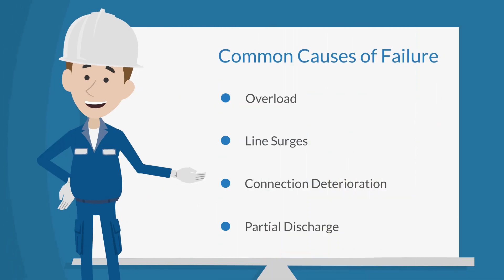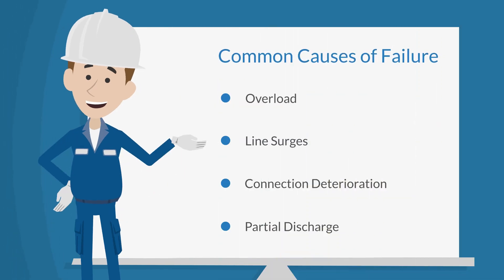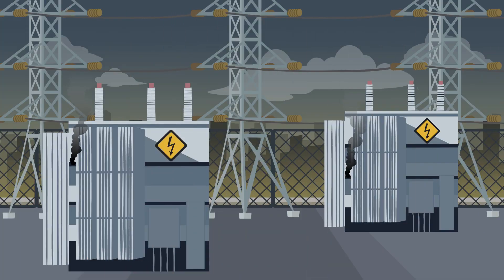Electrical transformer failures are either mechanical or electrical in nature. The common causes of transformer failures include overload, line surges, connection deterioration, and partial discharge, among others. Anything that causes the transformer to become hot will result in breakdown of the insulation, causing it to become brittle over time, eventually leading to a failure.